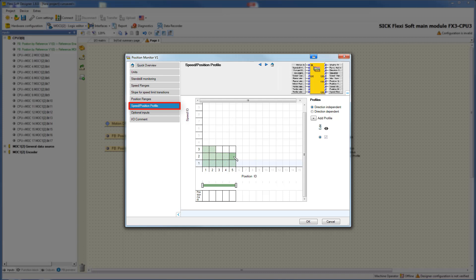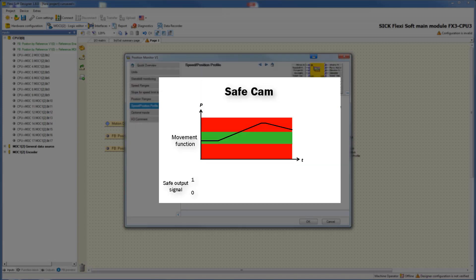In position range 1 and 2 it is allowed to move in every speed range. In position ranges 3, 4, and 5 it is only allowed to move in speed range 1 and 2, because speed range 3 is deactivated. To explain how to configure electronic cams, we have to take a look at the general explanation of the safety function safe cam.